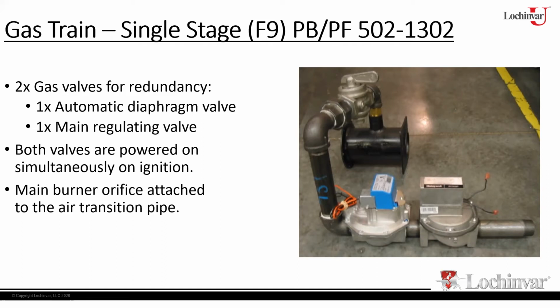Now the valves themselves, okay, the first valve, or the one closest to the manifold, this one right here, is your regulating gas valve. So that's the one you're going to adjust your pressure with. The other valve is just a standard open-closed. Both valves will be energized together, so they're wired in parallel. So when you energize one, you energize them both. They both open together at this point. Then the regulating valve controls how much pressure goes to that orifice. So again, this will be an on-off type operation. You only see these in retrofits. I don't see a whole lot of them, but they are out there. So it's just something to be aware of. It is a little bit different than your standard M9 configuration that you would see.